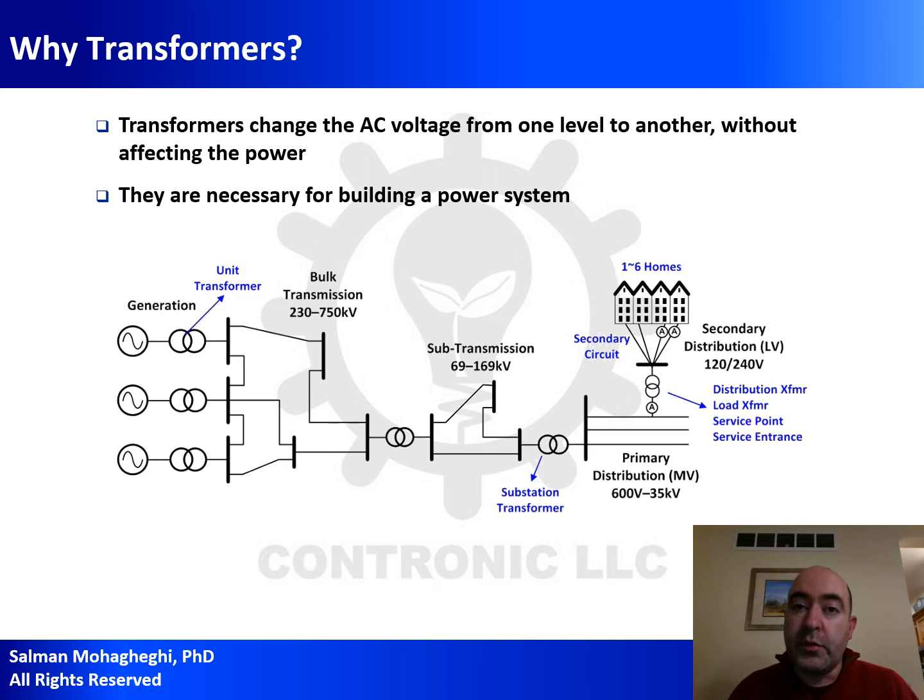Regardless of what you use, these lines are going to have resistances. And as a result, when the power goes from the generation side to the load side, the current flowing through this line is going to lead to ohmic losses, resistive losses, voltage drop. Typically, load areas are far away from generator areas, so that means you're going to have a significant voltage drop to an extent that the system is not going to be able to operate.